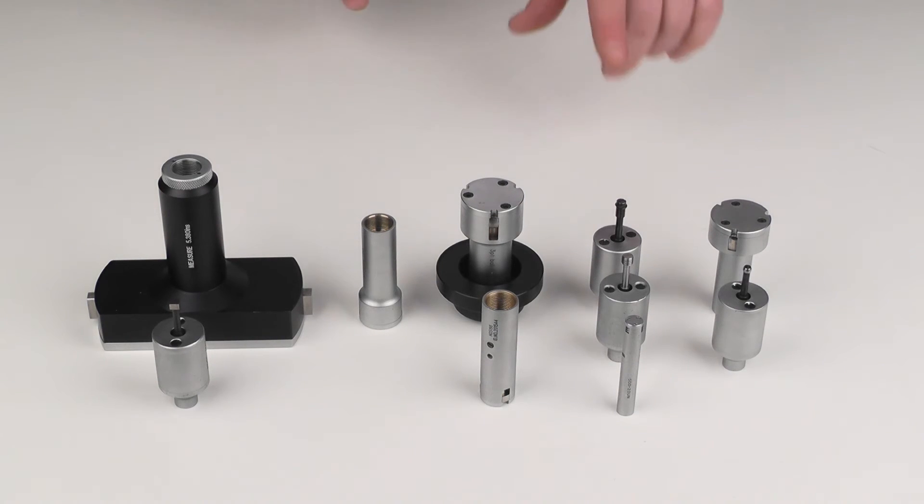So all of these except for the thread measuring heads can be set on a standard cylindrical master ring. The thread heads would have to have a threaded master ring with the nominal pitch diameter marked.